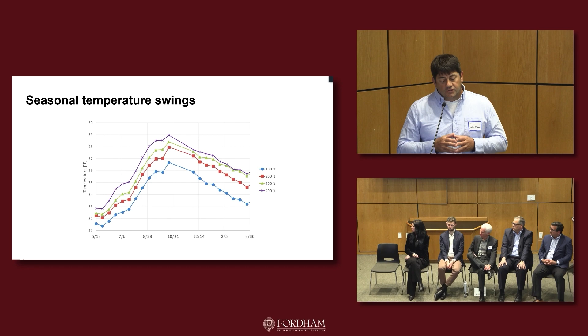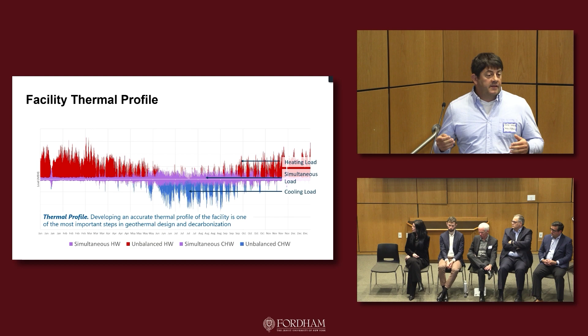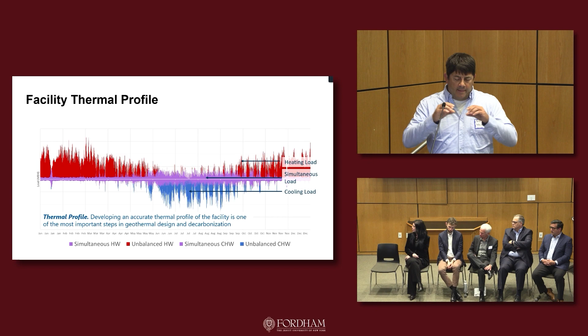Griff was talking about how, when you look at a building, we really want to reduce the energy first. Once you figure out that reduction, you know the energy you actually have to provide—but I'm not sure our energy models are accurate enough to really hone in on the exact size of heat pumps. There's always extra capacity in our equipment because of our thermal profile developments. We really strive today to figure out how much simultaneous load we can manage to downsize that air source, ground source, and exhaust air streams to capture all that energy.